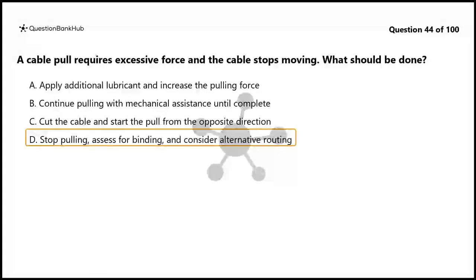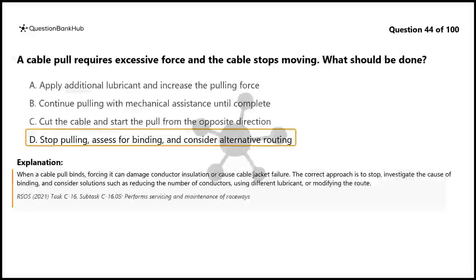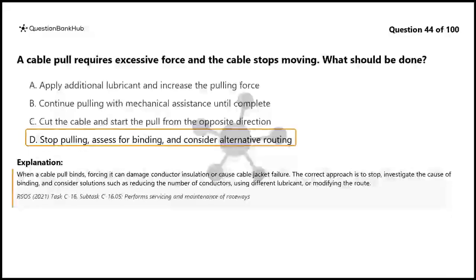The correct answer is D. Stop pulling, assess for binding, and consider alternative routing. When a cable pull binds, forcing it can damage conductor insulation or cause cable jacket failure. The correct approach is to stop, investigate the cause of binding, and consider solutions such as reducing the number of conductors, using different lubricant, or modifying the route.